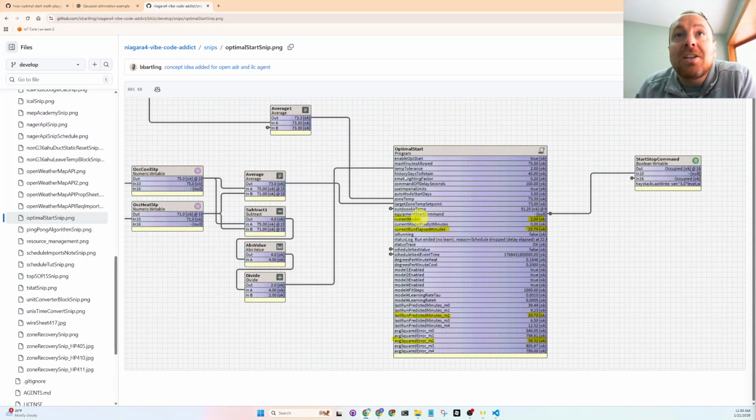So as you can see, this would be what a building automation system would look like. You wire in a sensor reading for outside air temp, schedule next value, schedule next event time, and then the model would be predicting minutes if we were predicting right here, but we're not. And then we recorded our last run of warm-up. So there are computer science patterns in here that are recording the start of the building automation system, and then it'll snapshot what that zone temperature was at that point in time, and also the target zone set point.